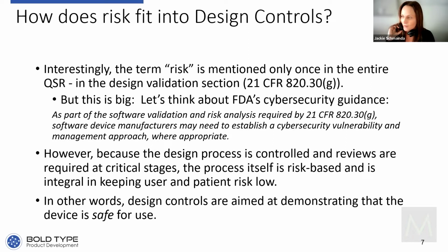It's also in the FDA cybersecurity guidance. So when you talk about cybersecurity and the risks related to wireless technology in terms of threats and vulnerabilities, the guidance itself actually references the design validation process. So there's a link there in terms of making sure that you have appropriate risks in the design control process. There are also design reviews at critical stages.